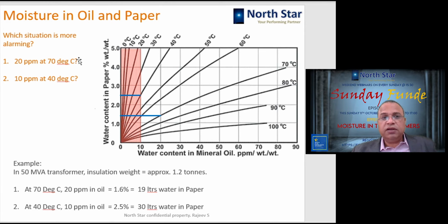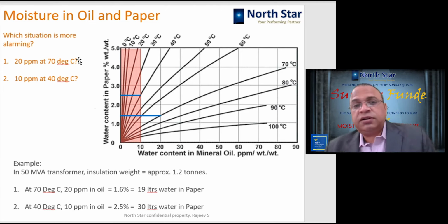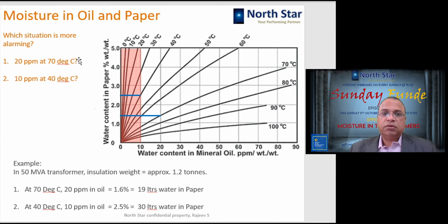When we look at the moisture in the paper, then we understand the actual condition of the insulation as far as the moisture effect is concerned. If we don't consider this aspect of moisture in paper, then we will say, okay, 10 ppm oil is good as compared to 20 ppm. So when you look at your test report, kindly look at what temperature the sample was taken and what the percentage moisture in the paper is. That will tell you what is happening inside.